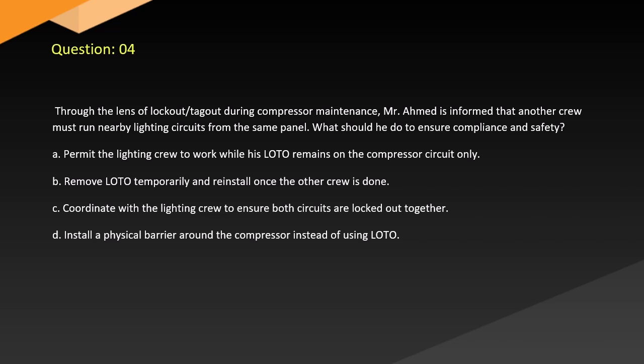Question 4. Through the lens of lockout/tagout during compressor maintenance, Mr. Ahmed is informed that another crew must run nearby lighting circuits from the same panel. What should he do to ensure compliance and safety? A. Permit the lighting crew to work while his LOTO remains on the compressor circuit only. B. Remove LOTO temporarily and reinstall once the other crew is done. C. Coordinate with the lighting crew to ensure both circuits are locked out together. D. Install a physical barrier around the compressor instead of using LOTO.